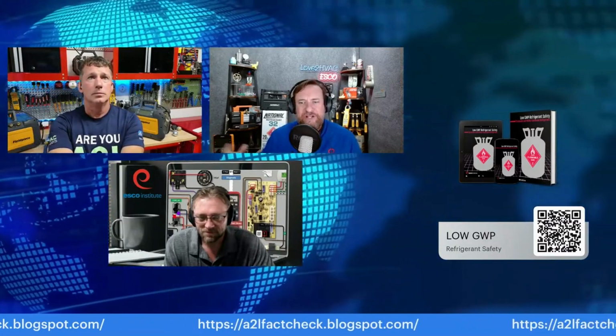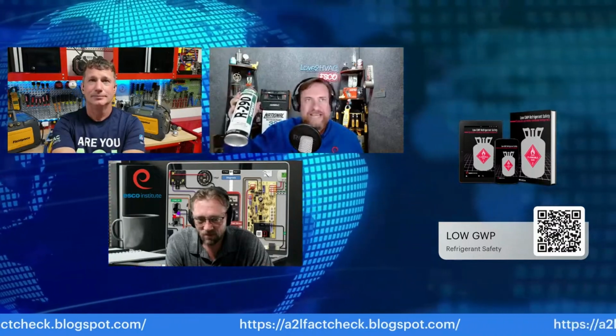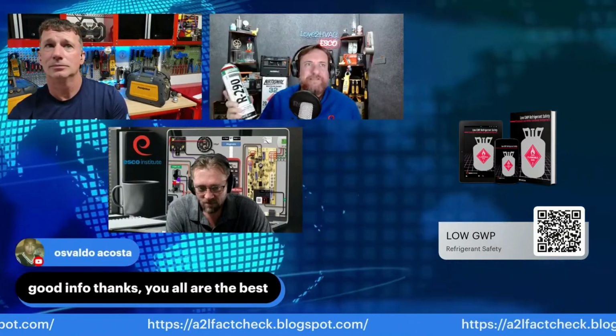And while we're talking about myth busting, one of the things I see on social media a lot is people complaining about a video they watched from another country where a refrigeration unit exploded, this window unit exploded, and there was a big fireball. That's not an A2L situation. It's also unsafe practices. If you notice, they're walking around in sandals, which is not OSHA. They're carrying units on ladders on their backs. They're not following safe practices to begin with. And you've got to think, even with propane right here, this will not have a flame unless I actually have oxygen with it. So even if I had propane in a system, I cannot have a flame unless there's oxygen.